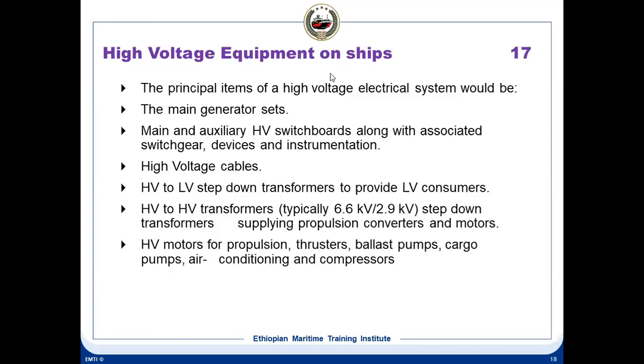Then HV to LV step down transformers to supply LV consumers. HV to LV means if you have 6600 volt, that has to be stepped down to 440 volt. Low voltage means it is 440 volt. So you'll find a lot of step down transformers for the low voltage consumers. This is also considered a high voltage equipment on ships. Then HV to HV transformers. There are some transformers from 6.6 kV to 2.9 or 3.3 kV. So they can say it is HV to HV. They use HV to HV step down transformers supplying propulsion converters, motors, etc.